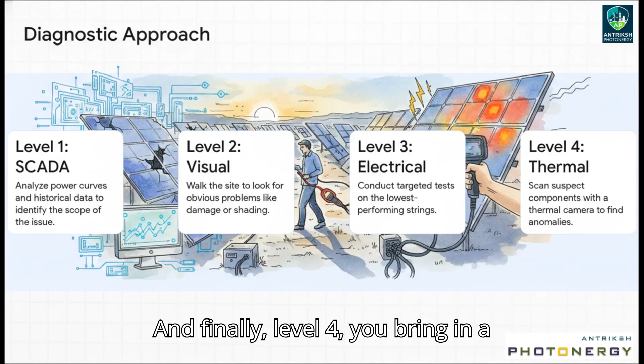This brings us to a really smart, multi-level approach. Level 1 is just you and the SCADA data. At level 2, you go on site for a visual check, look for the obvious stuff. For level 3, you get targeted: you use the data from level 1 to pinpoint the worst performing areas, and then you break out the electrical testing gear. And finally, level 4, you bring in a thermal camera to look for heat signatures the human eye just can't see.